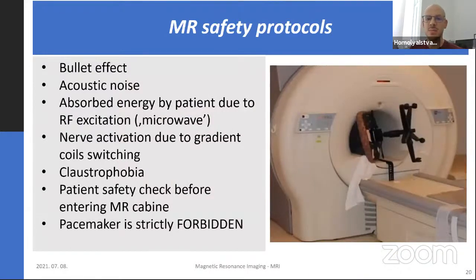And last but not least, let me emphasize the safety protocols of an MRI experiment. It's very important that nobody, including you if you are working with an MRI scanner, is allowed to enter the scanner room without precautions. Even if the scanner is not doing any measurements, the external magnetic field is present. It's always present. All right? So if you enter with a coin in your pocket or with a pen in your pocket, they can become bullets. And they are very, very dangerous for patients or others working in the same magnet room.